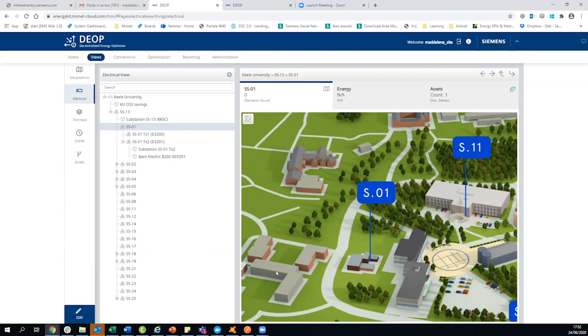So in these models, each type of asset has been modeled with its specific constraints and specific technological values. And the algorithm thinks in a forecasting direction. So it takes into account PV forecasting, takes into account energy consumption forecast, and is determining an optimal scheduling of the different assets according to an optimization objective.